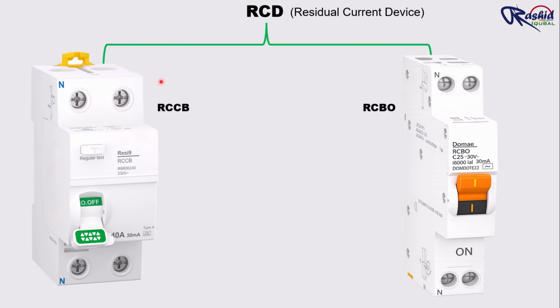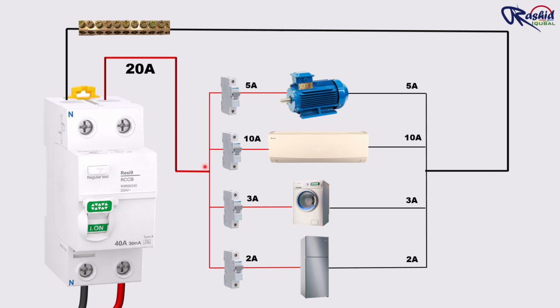Now let's understand how an RCCB actually works with a practical example. Assume we have 4 loads connected in a house: a motor, air conditioner, washing machine and a refrigerator. Each load is protected by its own MCB. Here you can see these are all protected with their own MCB, while all of them are supplied through one common RCCB. This is the common RCCB. Under normal operating conditions, the motor consumes 5 ampere current, air conditioner 10 ampere, washing machine 3 ampere and refrigerator 2 ampere. I just assume these ampere ratings for this equipment.